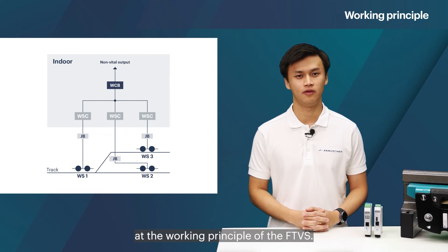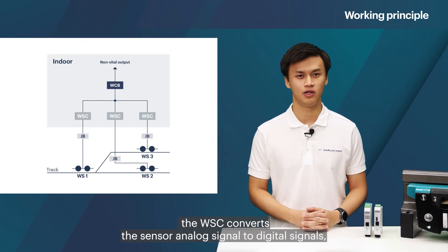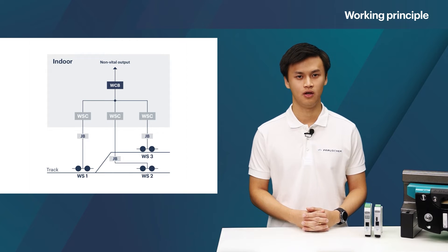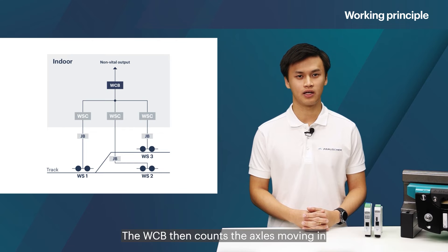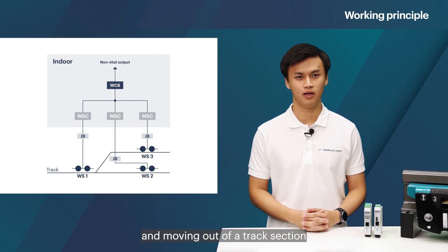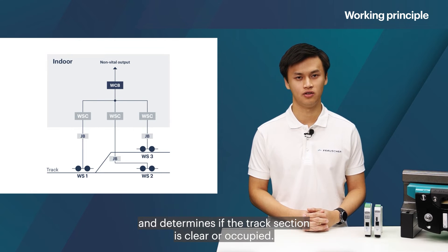Now let's have a closer look at the working principle of the FTVS. If a rail vehicle traverses an RSR110, the WSC converts the sensor analog signal to digital signals, which are then fed into the WCB. The WCB then counts the axles moving in and moving out of the track section and determines if the track section is clear or occupied.